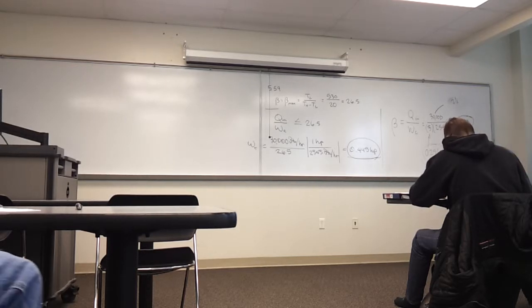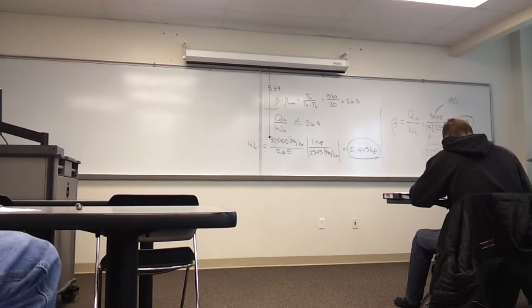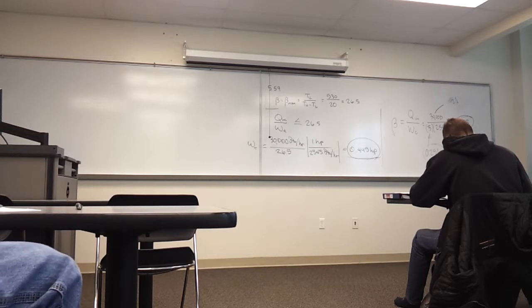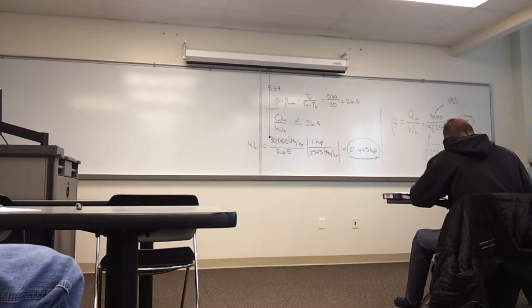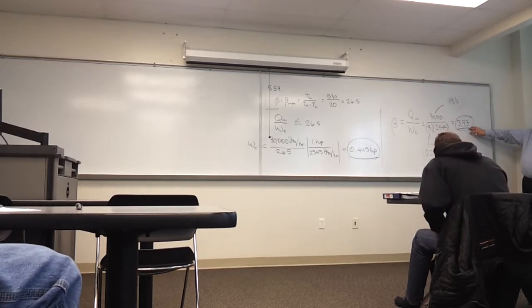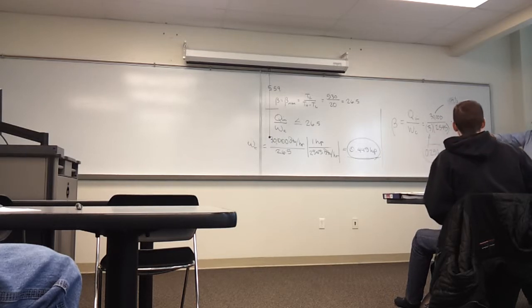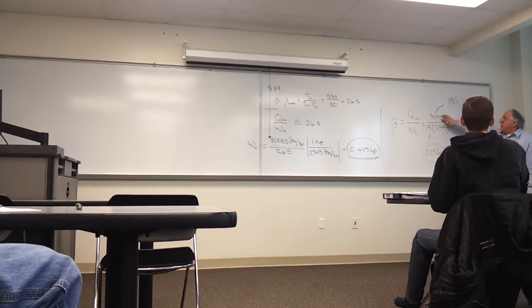Because all it seems like it's doing is changing the compressor on it. If we are looking at this, all I would do is just go buy a half-horse compressor, plug it in, and it would work perfectly fine. But is that not true? No, a half-horse compressor would not work perfectly fine. And why is that? Because the real system would probably only have a COP of 4, and if you had a half-horse compressor, you might only be able to transfer about 6,000. Yeah, but how can we judge what the rest of the system is doing if all we're changing is just the work of the compressor?